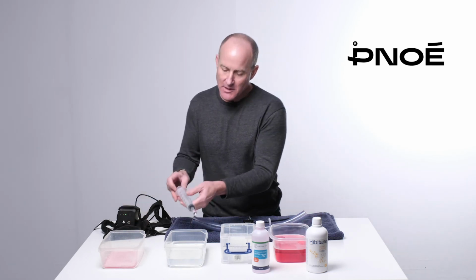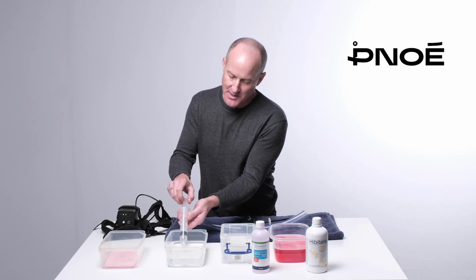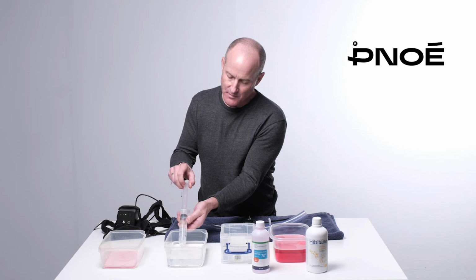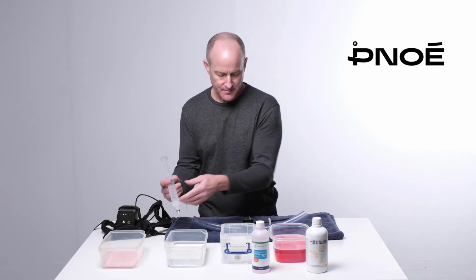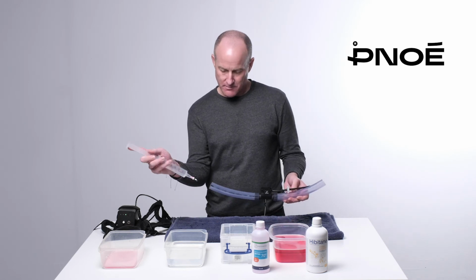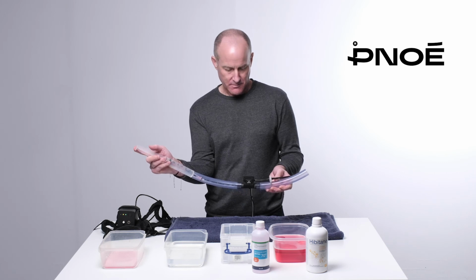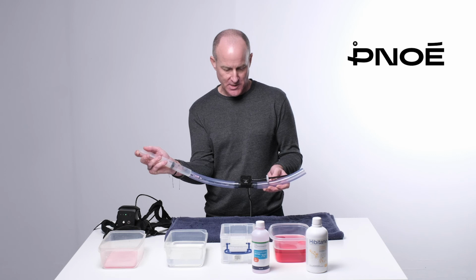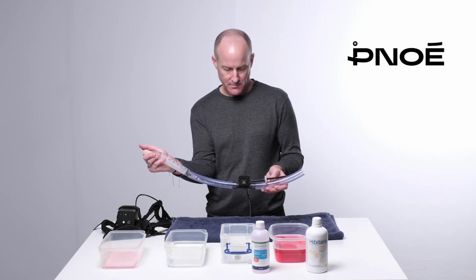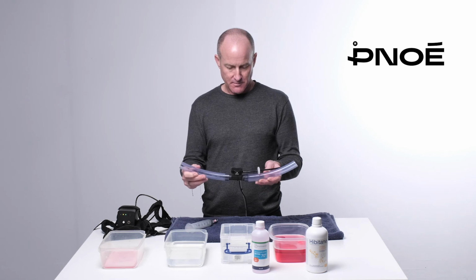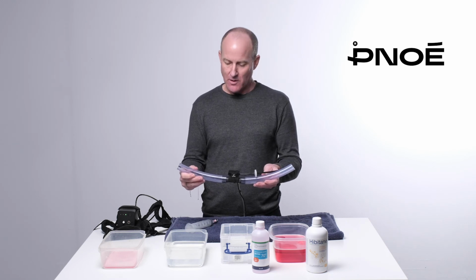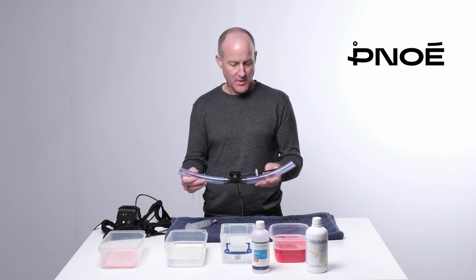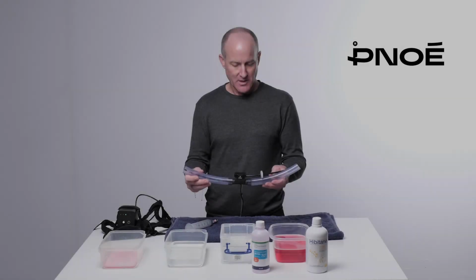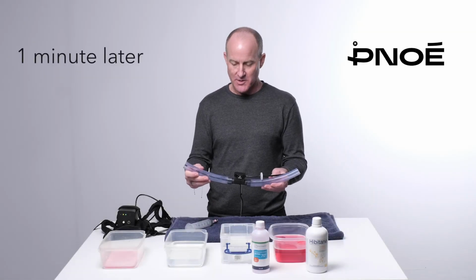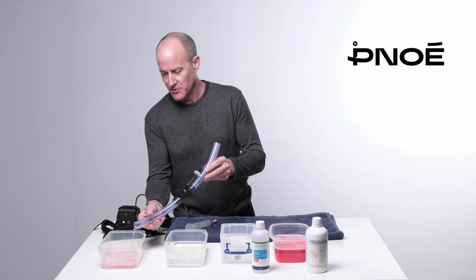And you're going to put in 60 mils of deionized water. This is to rinse out the flow sensor completely prior to its next use. About 1 minute of rinsing here by just rocking back and forth. And then after 1 minute of rocking to make sure that it's fully clean, you're going to dump out that solution as well.